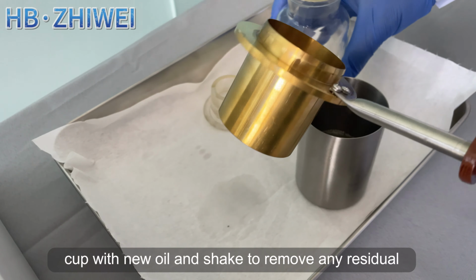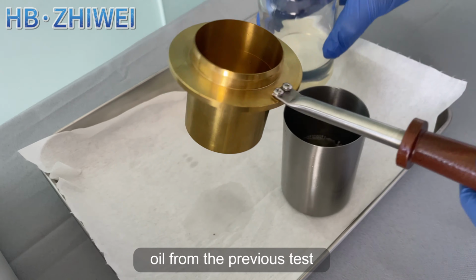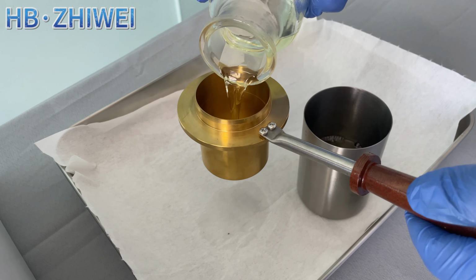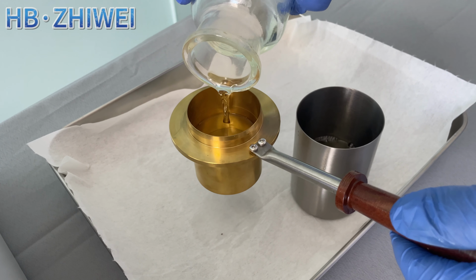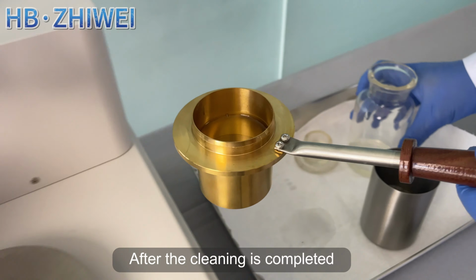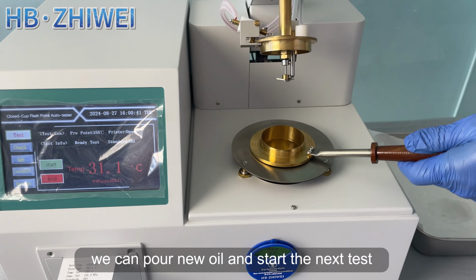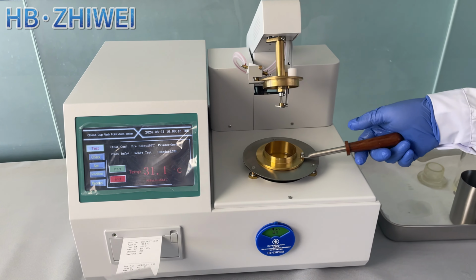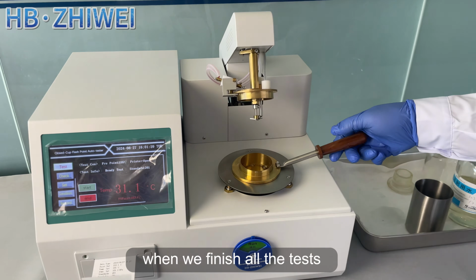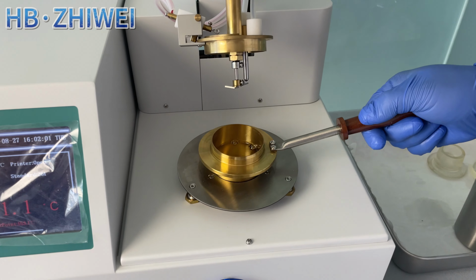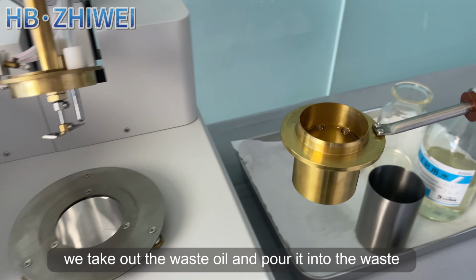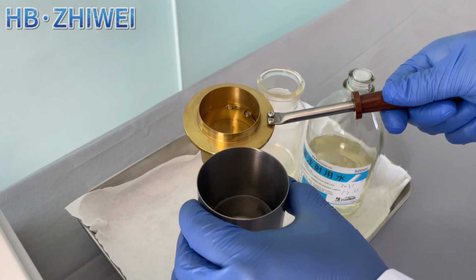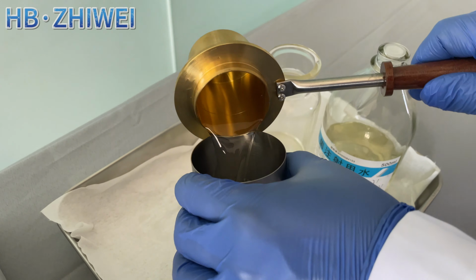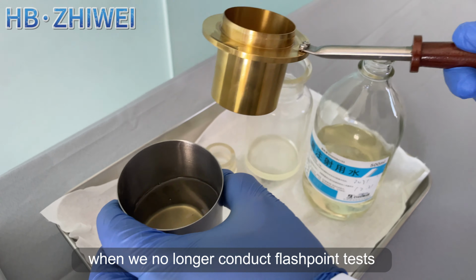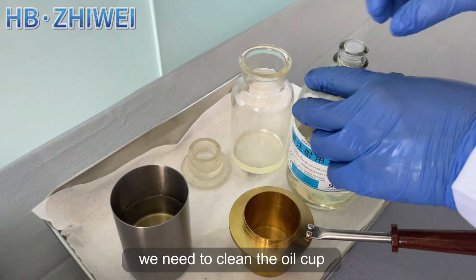Rinse the oil cup with new oil and shake to remove any residual oil from the previous test. After the cleaning is completed, we can pour new oil and start the next test. When we finish all the tests, we take out the waste oil and pour it into the waste oil cup. When we no longer conduct flashpoint tests in a short period of time, we need to clean the oil cup.